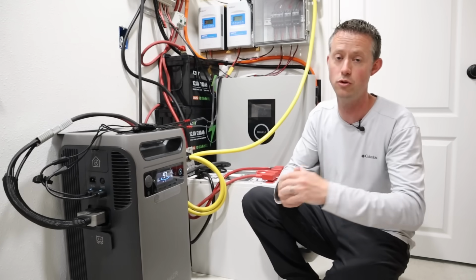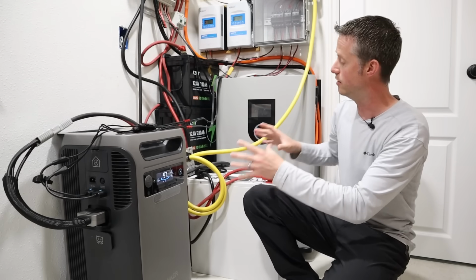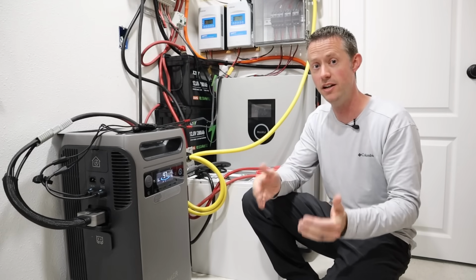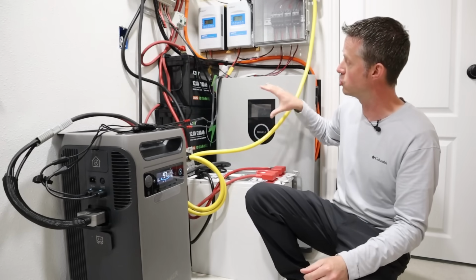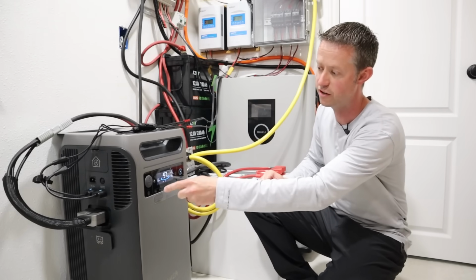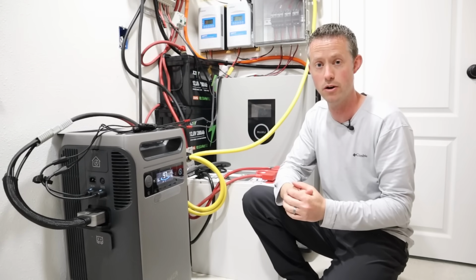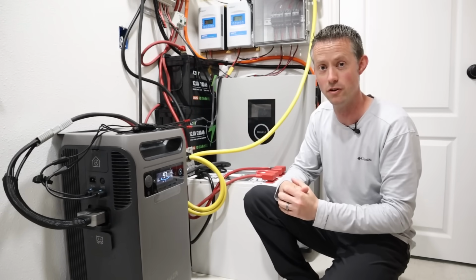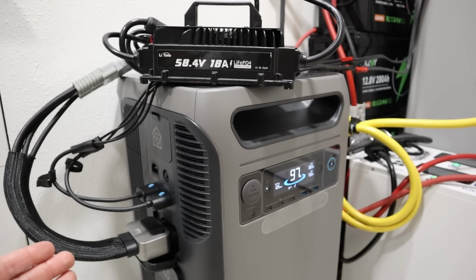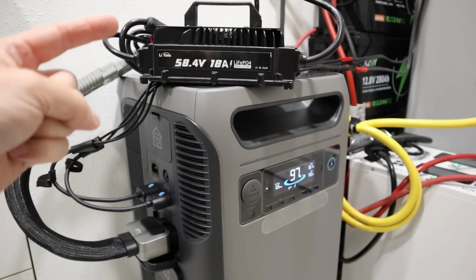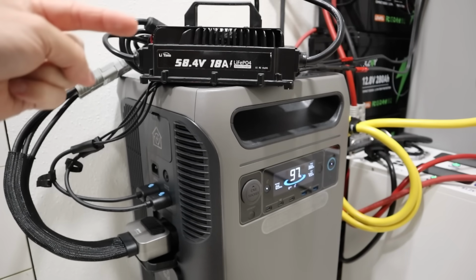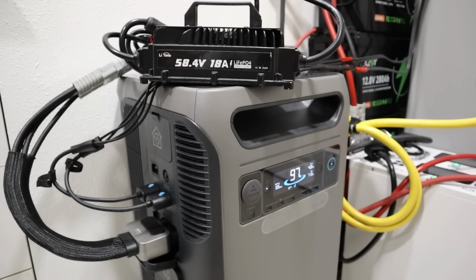There's only one issue you have to worry about when you're doing this sort of modification, and it's actually if you get these batteries charged up too high, or if you have too high of voltage connected up the expansion battery port, it's going to shut off the inverter. So how much voltage is too much voltage? Well, I was using this lithium iron phosphate battery charger to top off the entire system. You'll notice right here it says 58.4 volts.